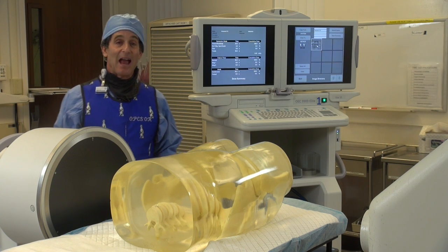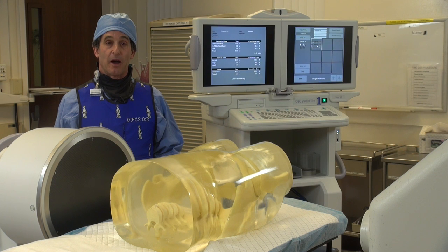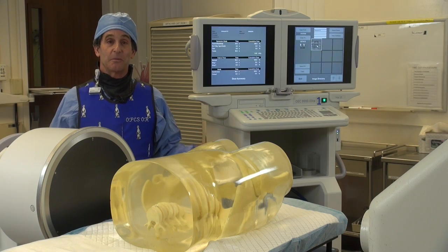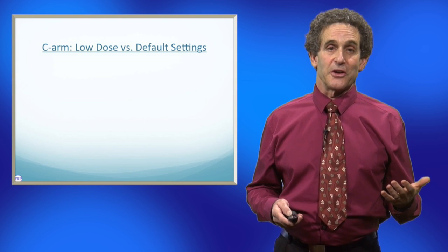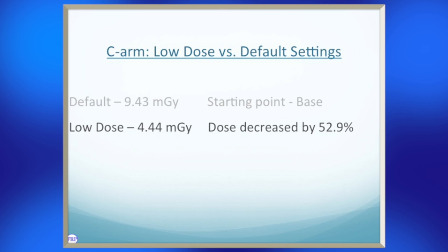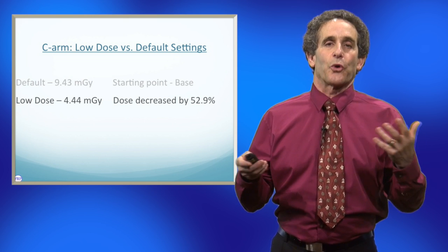So it's a spectacular way of saving dose to your patient. You just have to sometimes worry that it might be a little mottled. But when it's not, you've saved half the dose to your patient and everybody in the room — so that's definitely the way to go. Here was the low-dose versus default settings with the C-arm: default came out at 9.43 milligray, and when we went down to low-dose, it dropped to 4.44 milligray. The dose decrease was 52.9% — basically cut it in half. And historically, that's always what it'll do.